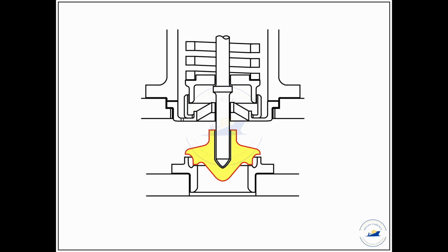Next, we have to carry out a thorough inspection of the valve spindle, as in the straightness of the valve spindle has to be inspected. That can be done after completely disassembling and checking it with the help of a gauge or checking it on the lathe as well. Once the straightness has been checked thoroughly, the valve spindle has to be checked for other defects, such as surface cracks, interstitial cracks, small impingement action, and other corrosive defects as well. The valve spindle has to be thoroughly cleaned and made sure that it is completely rust free and there is no debris in the way.